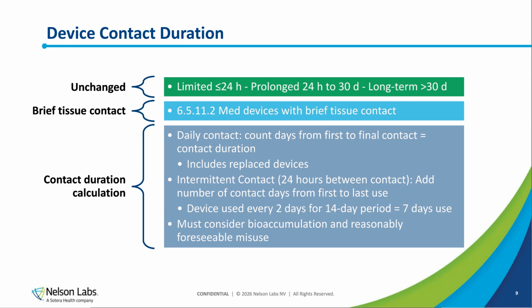Now, really, the meat of the change is where you do your contact duration calculation. So basically, any contact now is a daily contact. So you count the days from the first to final contact, and that's your contact duration. That also includes replaced devices. So if your device contacts a patient 5 minutes one day and then 5 minutes a second day, that's not 10 minutes of contact, that's actually 2 days of contact.